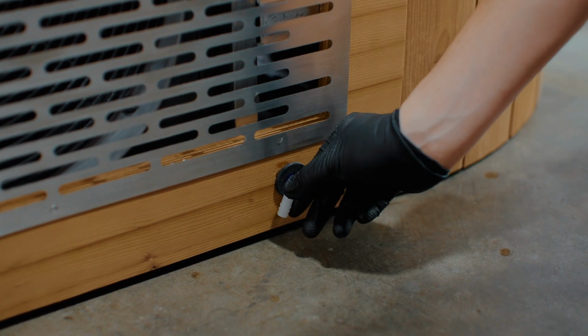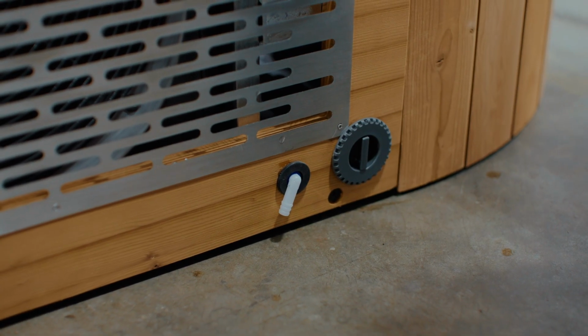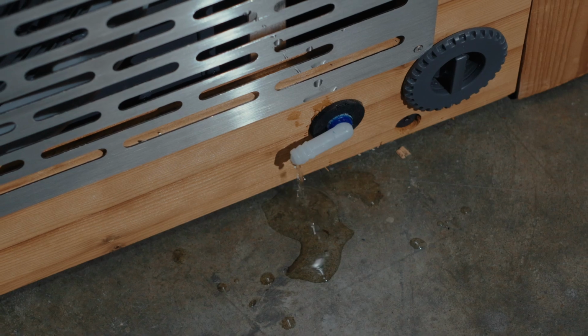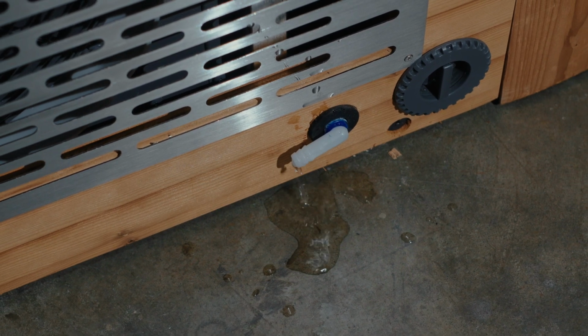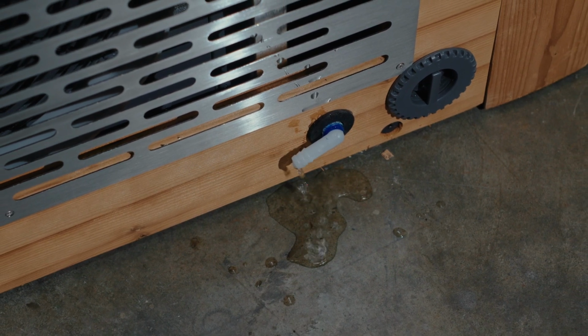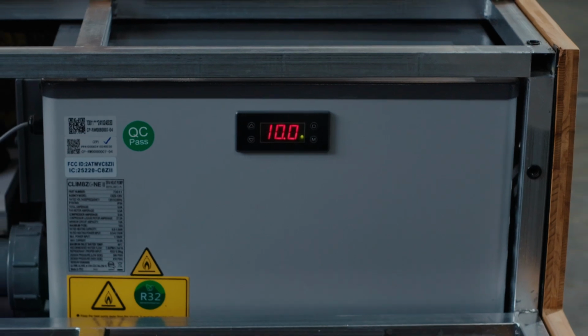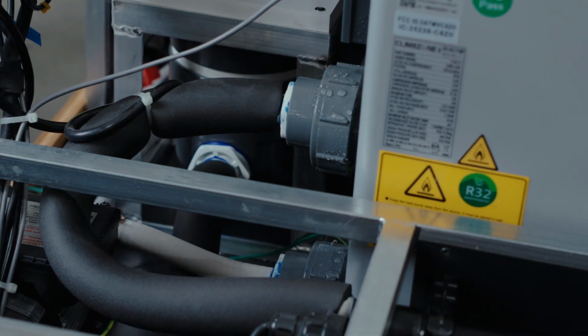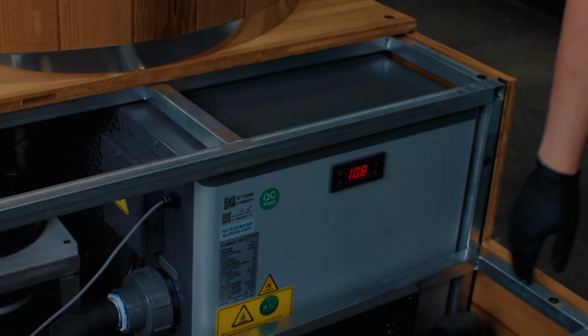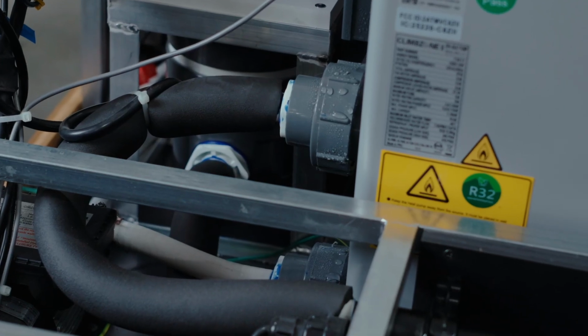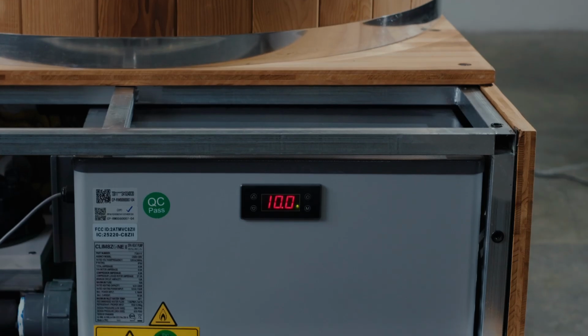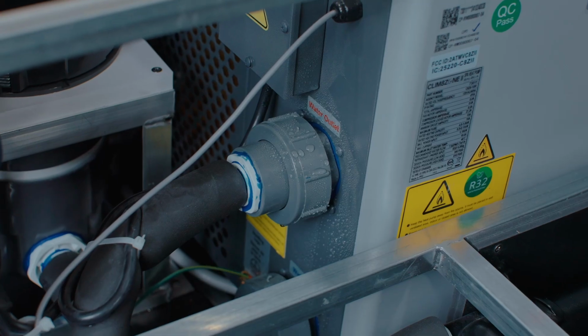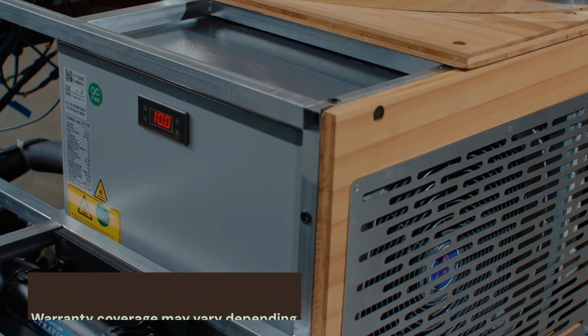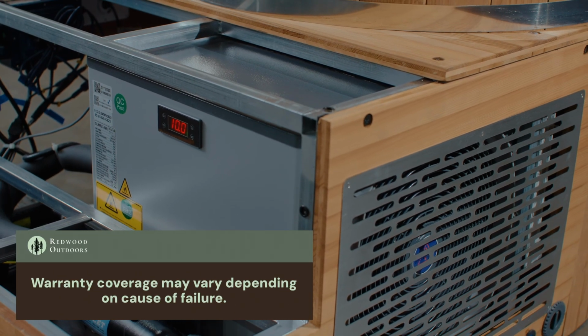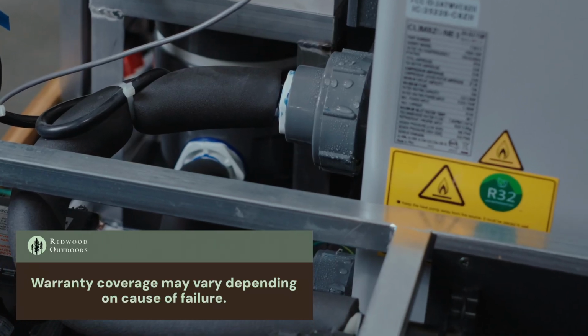During normal operation, the condensation drain will periodically release small amounts of water. A constant or excessive flow from the condensation drain may indicate an internal issue rather than normal condensation. The Balboa Chiller housing should generally not be opened during standard field diagnosis unless specifically directed by Redwood Outdoors Support. If the leak is confirmed to originate from inside the Balboa Chiller assembly, the complete chiller unit will typically require replacement rather than repair. Warranty eligibility may vary depending on factors such as freeze damage, maintenance history, unit age, and overall system condition.